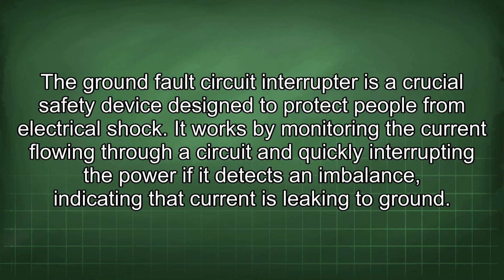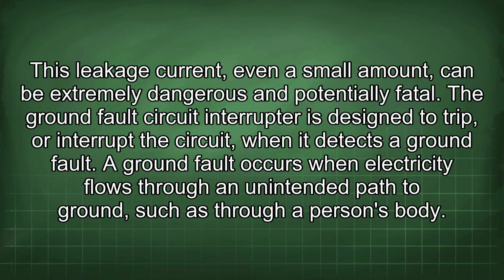the job. The ground fault circuit interrupter is a crucial safety device designed to protect people from electrical shock. It works by monitoring the current flowing through a circuit and quickly interrupting the power if it detects an imbalance, indicating that current is leaking to ground. This leakage current, even a small amount, can be extremely dangerous and potentially fatal.